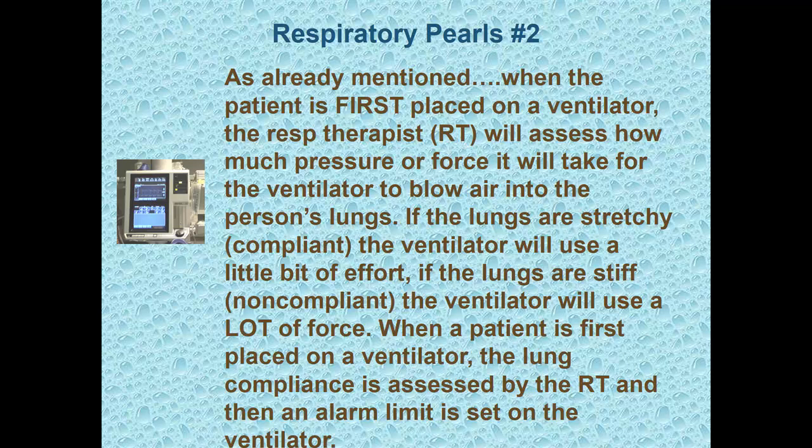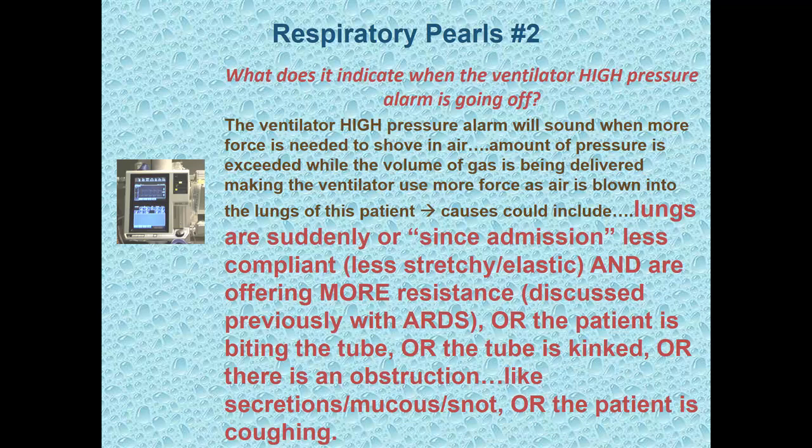So that means that if the high pressure alarm is going off, then instead of the normal 30 amount of pressure that the ventilator has to exert to get air in the lungs, it's having to use a lot more force to push in air. And if it's a really great number, then it's going to keep alarming. So what's the big deal with this? Well, the big deal is that the ventilator is not able to deliver air. So your patient's not being ventilated.